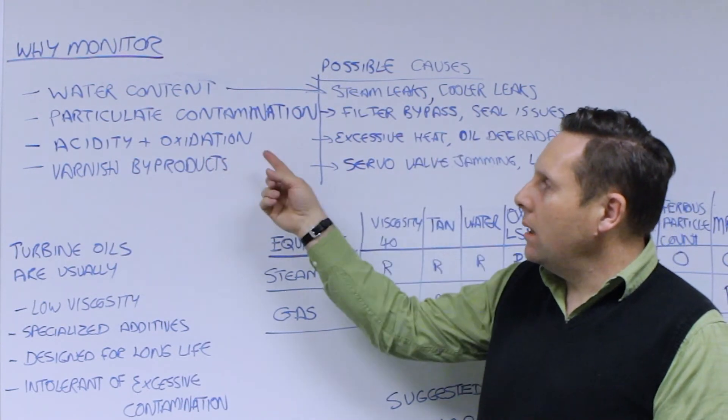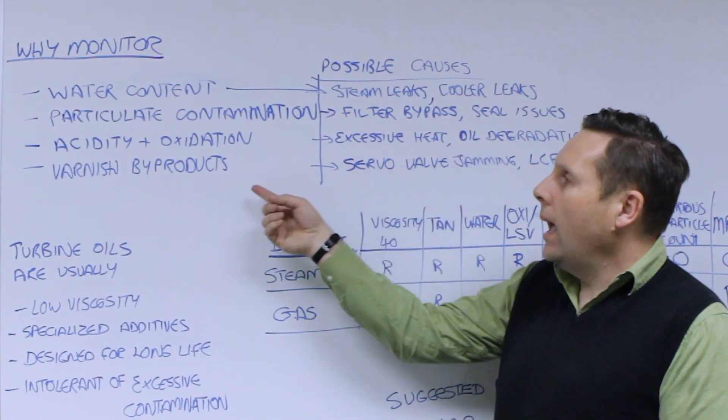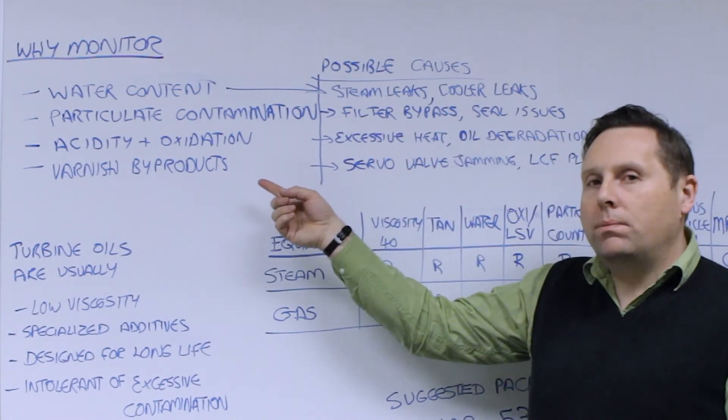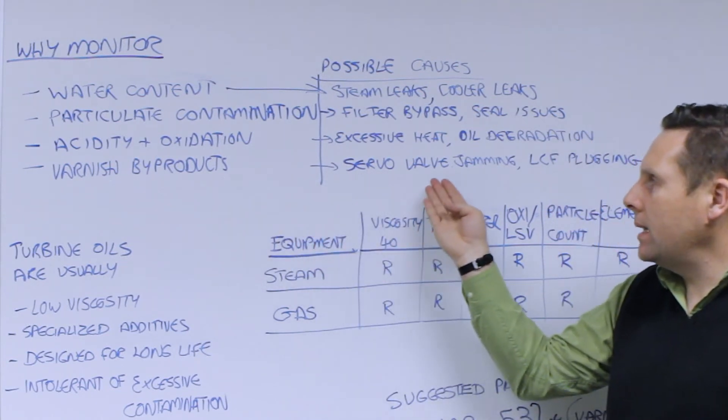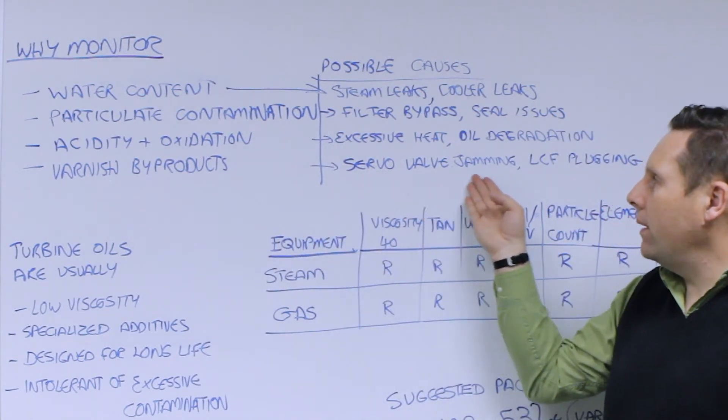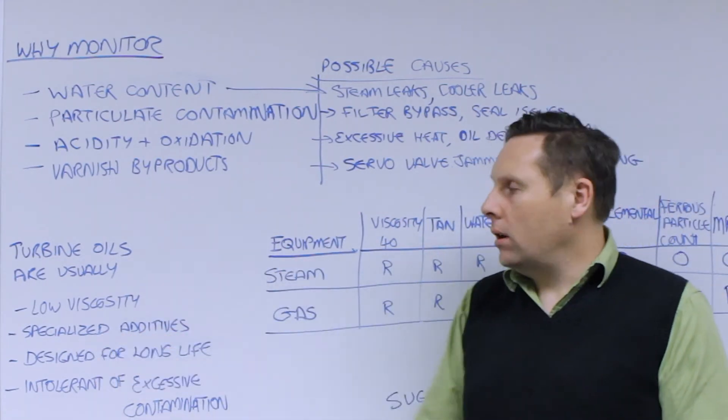We want to always monitor acidity and oxidation because it can indicate excessive heat or oil degradation and also we want to look for varnish byproducts on the certain designs which are susceptible to that because that can lead to servo valve jamming or last chance filter plugging particularly in the hydraulic control systems.